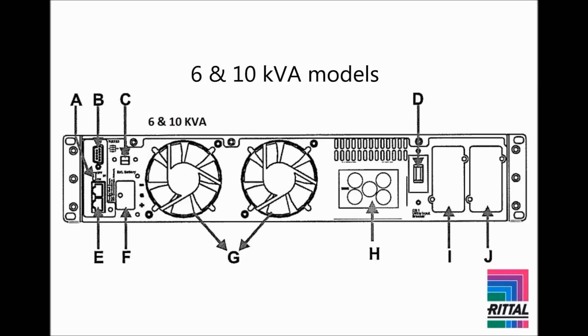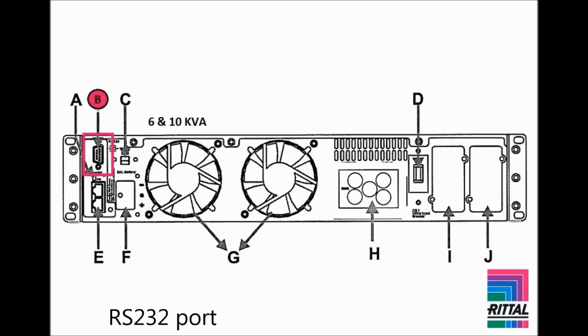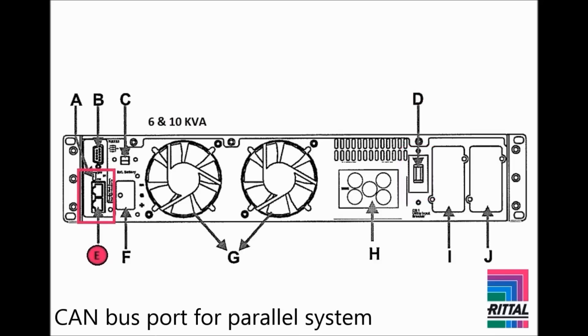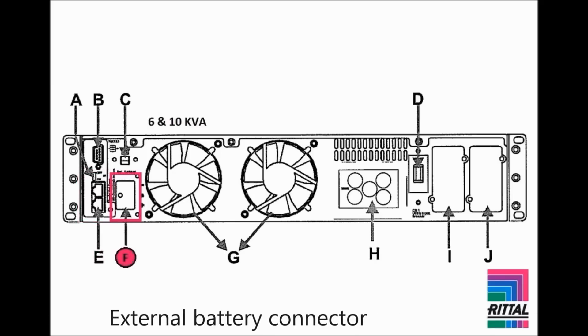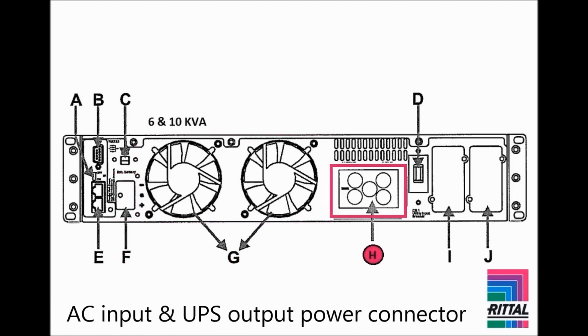The rear panels of the 6 and 10 kVA models are identical. You find a terminal resistor used for paralleling PMC-12 units. The communication port provides a true RS-232 serial interface which can be used with the free software to remotely monitor power and UPS status. There is an emergency power-off port. The AC input circuit breaker is a feature unique to the 6 and 10 kVA models of the PMC-12. So is the CAN bus port, which is used as a data interface when paralleling PMC-12 units. External battery packs can be connected to the external battery connector. There are two cooling fans. The 6 and 10 kVA models feature a combined AC input and UPS output power connector.